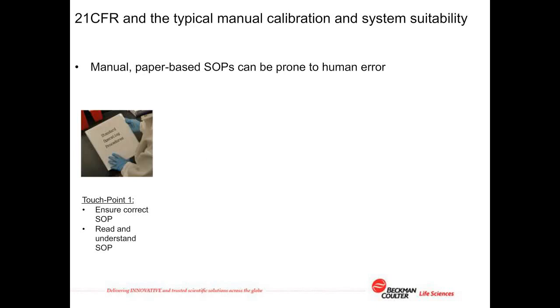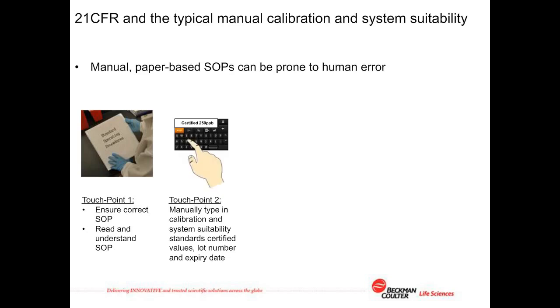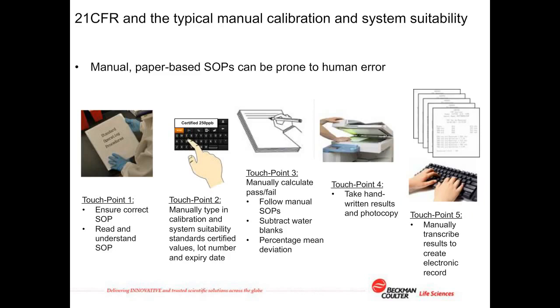Now, there are 21 CFR Part 11 issues with the typical instrument calibration and system suitability testing, with many manual SOP steps to be followed in the typical water monitoring process. Values for certified standards used in the calibration process are manually typed into the TOC analyzer for both calibration and system suitability, inviting human error and mistyping. Pass-fail reports have to be manually calculated, and finally the electronic record is created by photocopying the manual calculations and manually typing the results into the system, and all of these steps can be prone to human error, leading to 21 CFR Part 11 integrity issues.